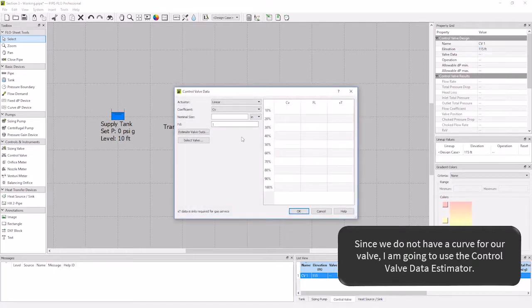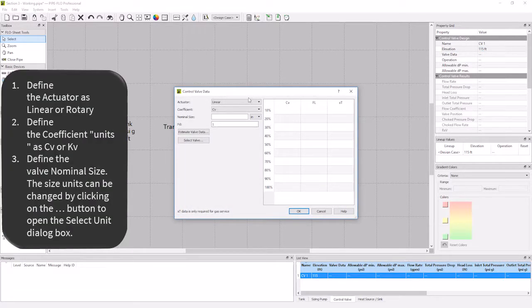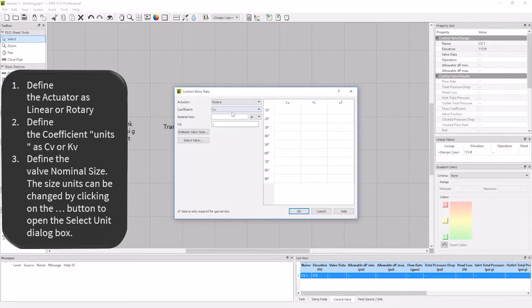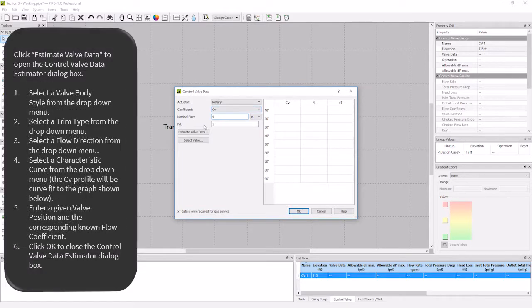I am going to set the actuator to rotary and leave my coefficient set to CV. My nominal size of my valve is 4 inches, and now I'm going to open the valve data estimator to fill in the rest of the data.